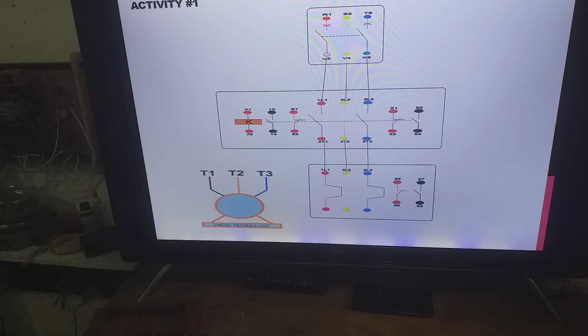So this is the power diagram. In this activity, the power diagram runs from the source to the circuit breaker, to the magnetic contactor, to the thermal overload relay, to the motor. Take note that in the power diagram of industrial motor control, if your motor is rated at, say, 10 horsepower, your circuit breaker, magnetic contactor, thermal overload relay, and even the wire you connect must also be sized for 10 horsepower.